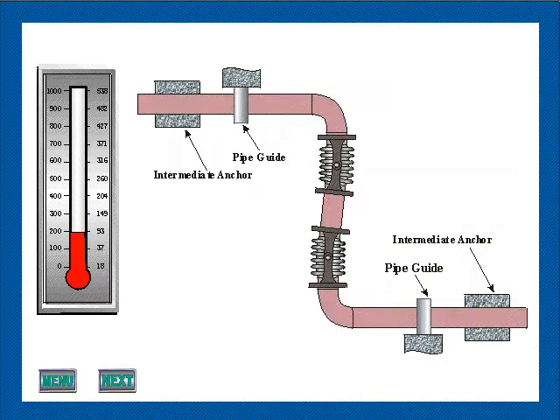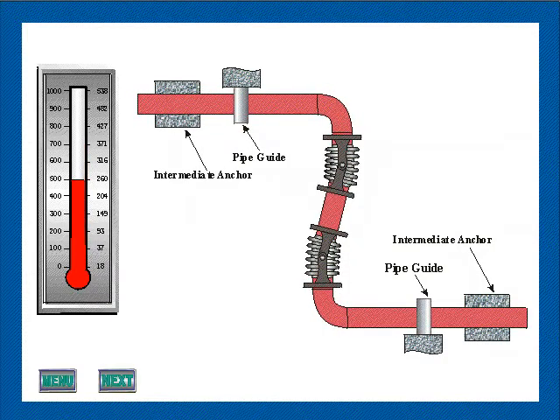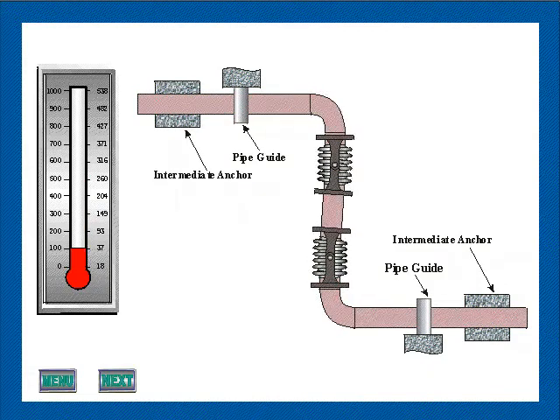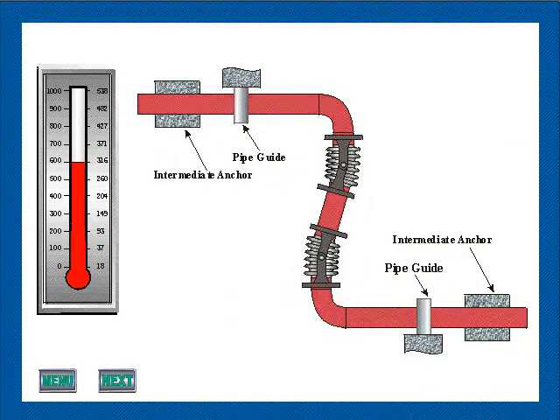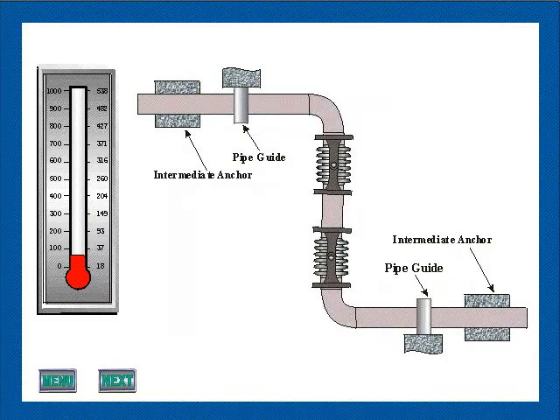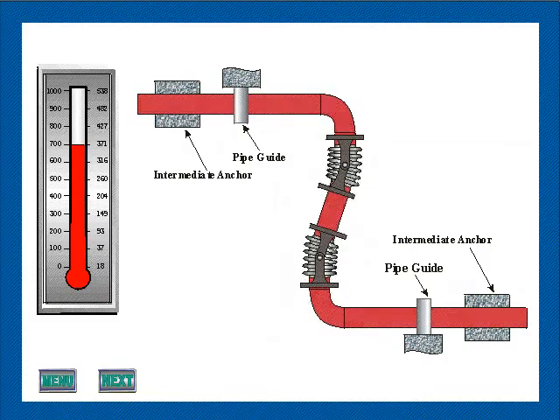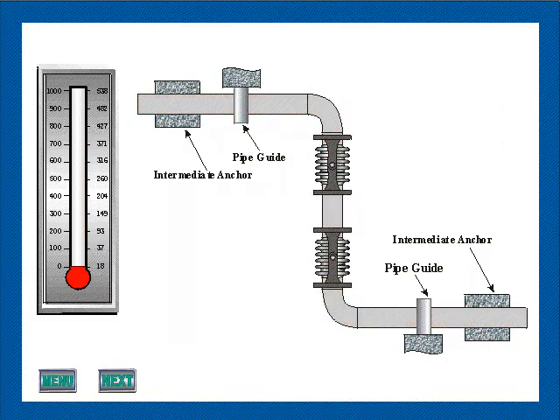The thermal expansion of the offset section containing the expansion joints must be absorbed by bending of the piping legs perpendicular to that segment. Since the expansion joints are restricted to pure angular rotation by their hinges and cannot extend or compress.